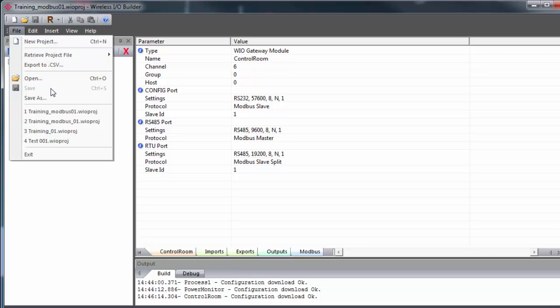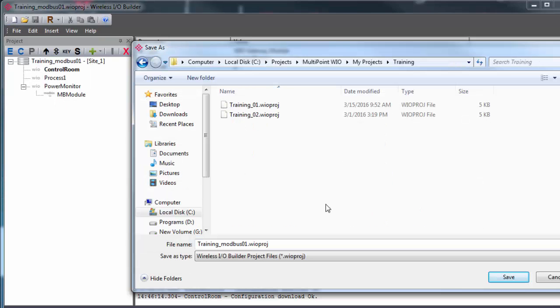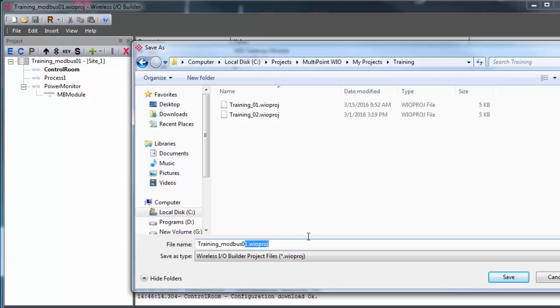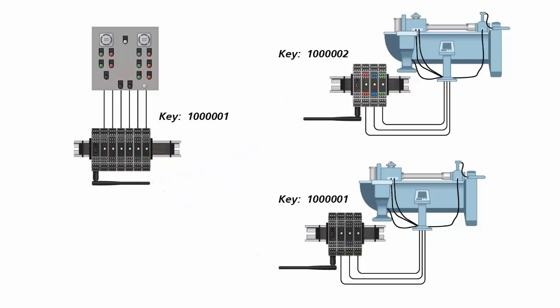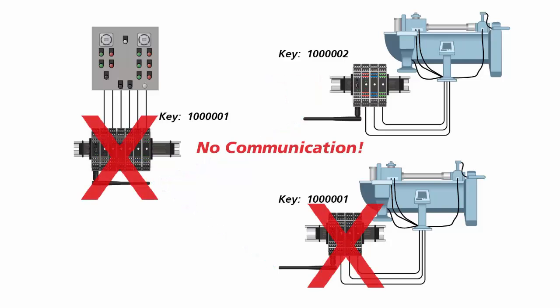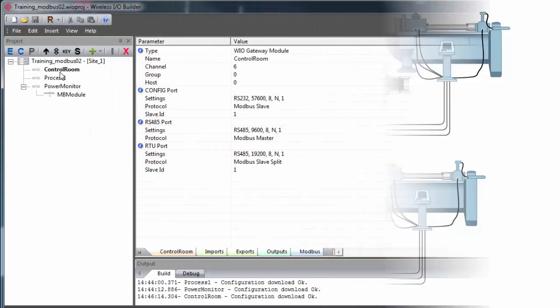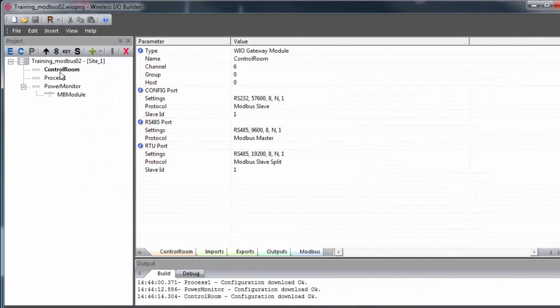Note that if you go up to File and Save As, this will be regarded as a new configuration file and generate a new key. Any groups within a network that are updated with this new file could be assigned the new key, and they would then be unable to communicate with any other groups on the network. Keep in mind, if you're setting up a gateway for the first time, it'll update the configuration without incident.